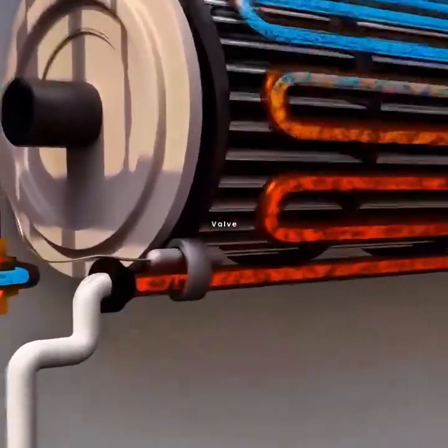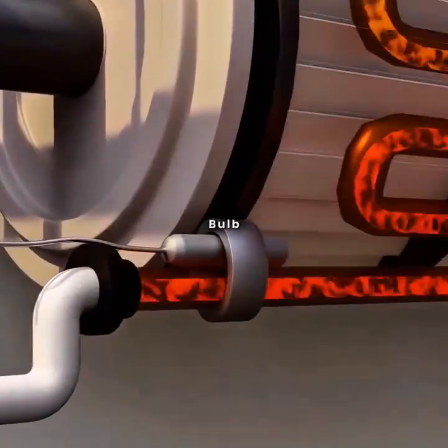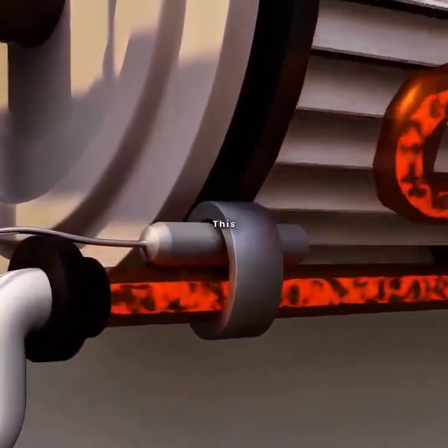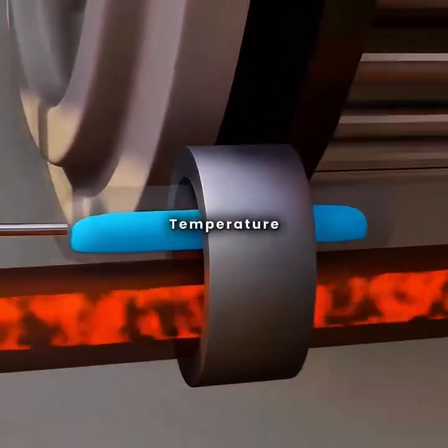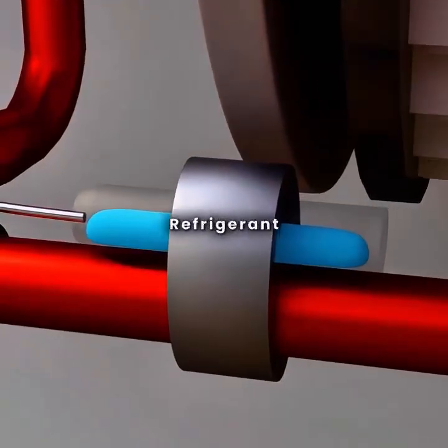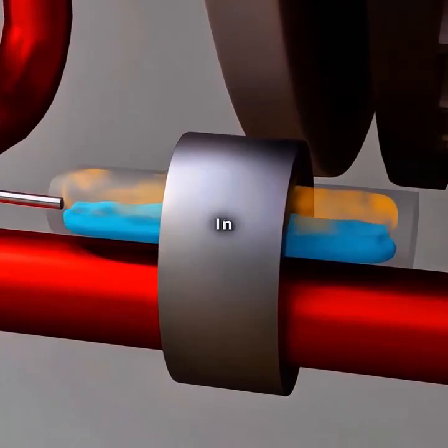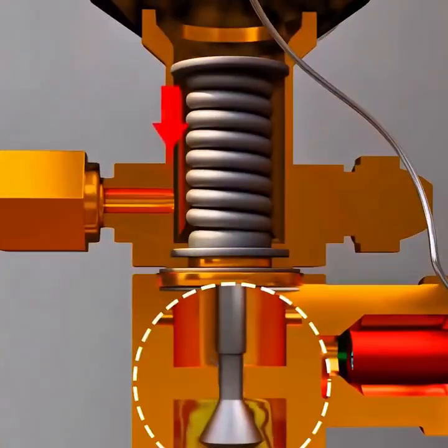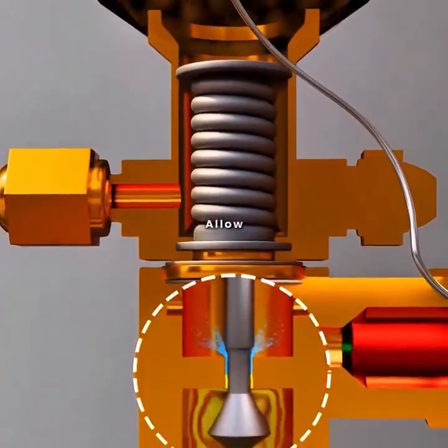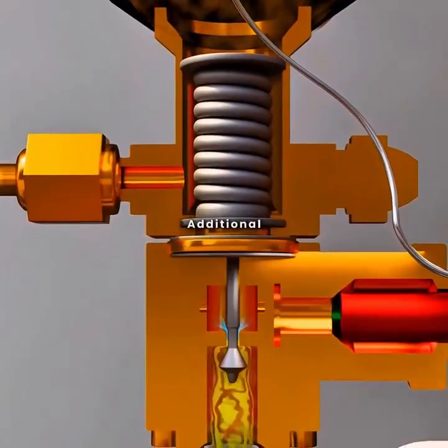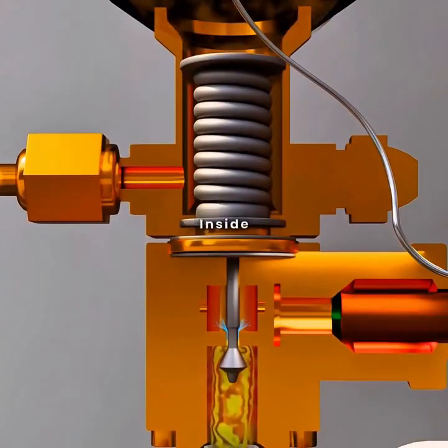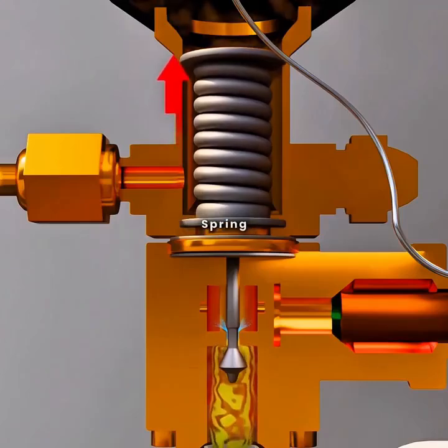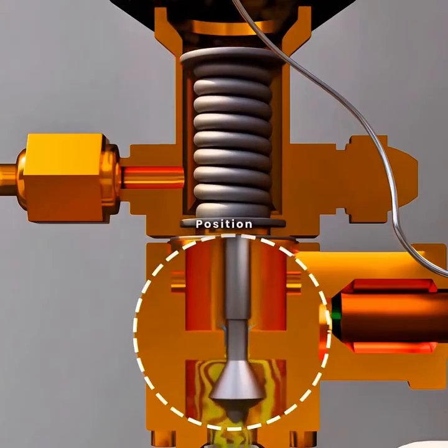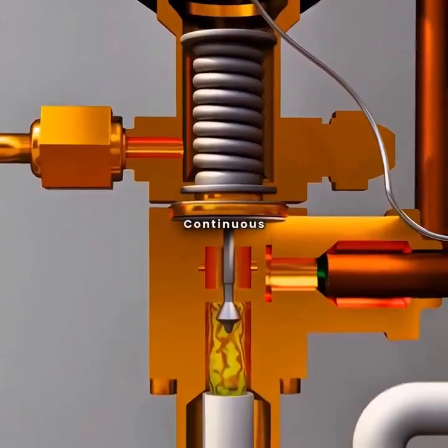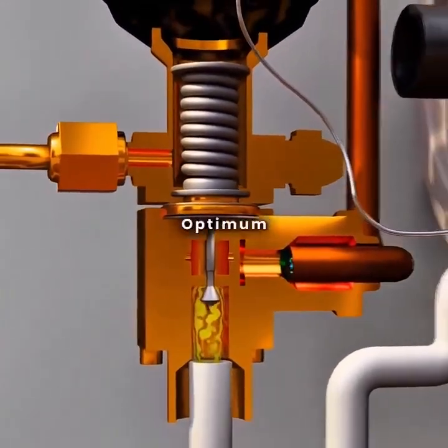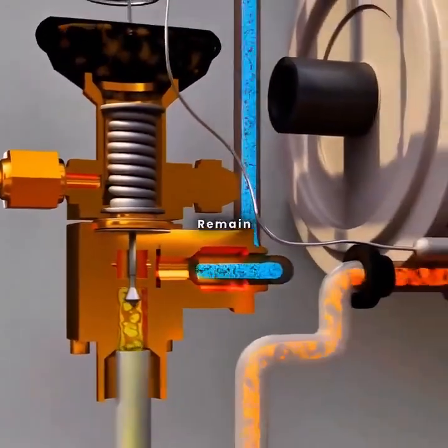You'll find that the expansion valve is connected to a slender temperature-sensing bulb attached to the outlet of the evaporator. This bulb also contains refrigerant. When the temperature of the evaporator outlet rises, the refrigerant inside the sensing bulb boils, increasing its pressure. That pressure is transmitted to the expansion valve, causing it to open wider and allow more refrigerant into the evaporator to absorb additional heat. When the outlet temperature falls, the pressure inside the sensing bulb decreases. A spring pushes the valve toward the closed position, reducing the refrigerant flow. This continuous adjustment keeps the evaporator operating at its optimum condition, allowing the room temperature to remain stable.